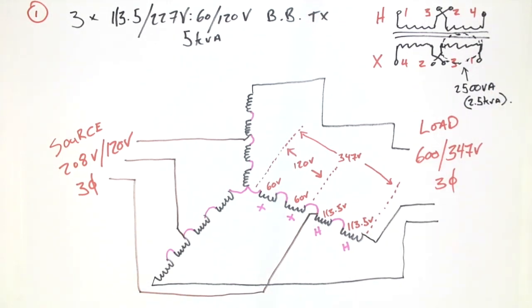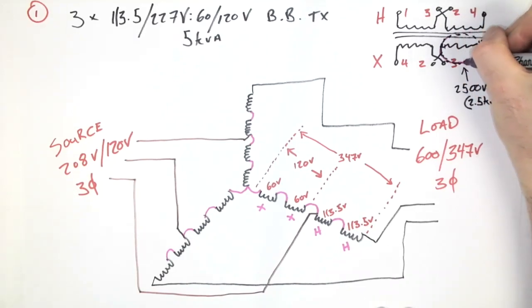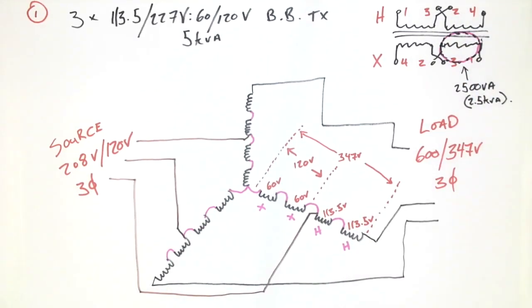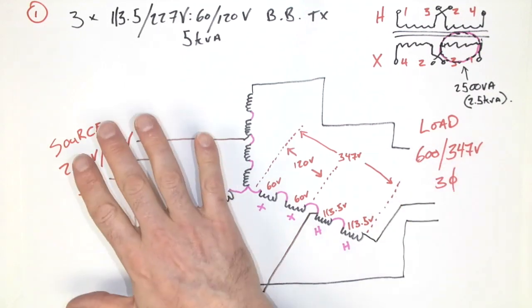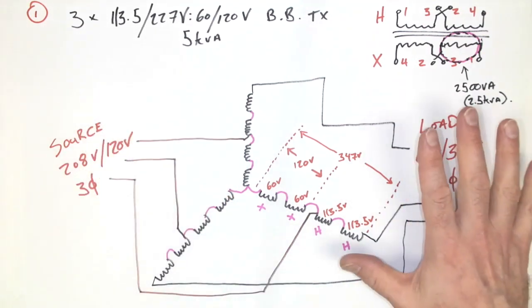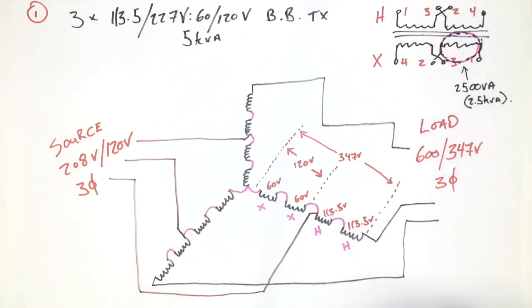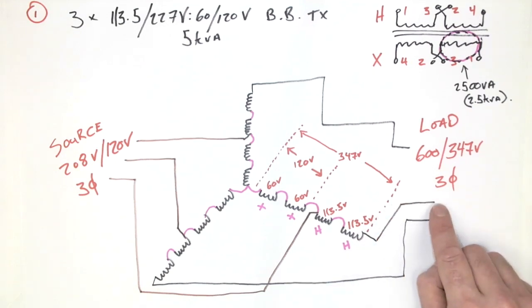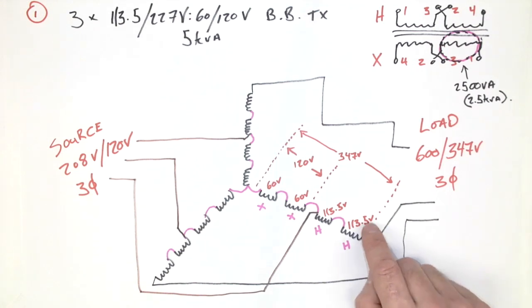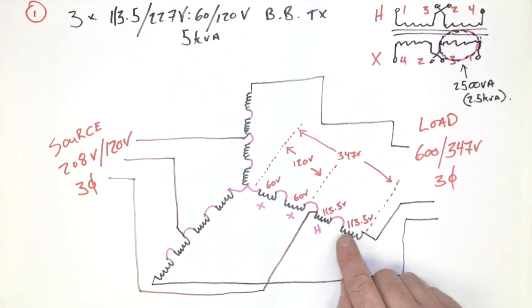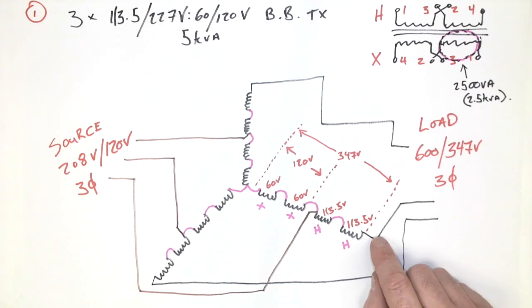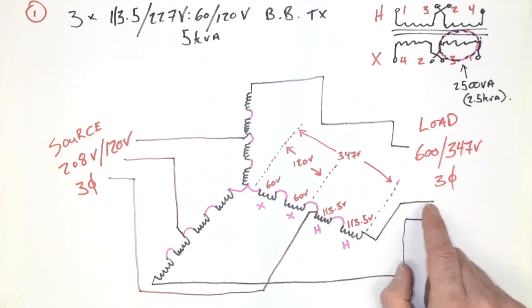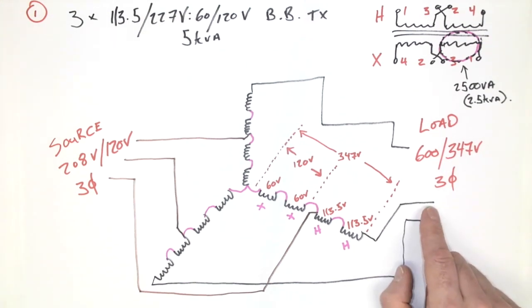Now with this information, what I'm going to do is find a series connection somewhere in the circuit. It doesn't have to be the supply, and it doesn't have to be the load. I'm looking for a series connection between a winding and the line conductor that supplies or is being supplied. And I see it right here. I've got one high side winding, and it is in series with my 600 volt, 347 volt load.